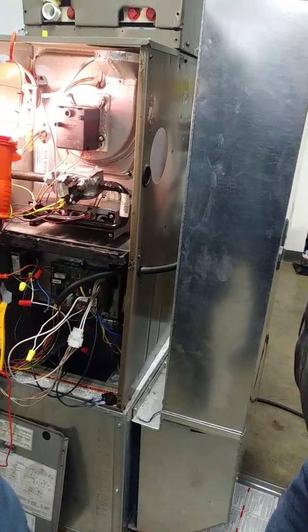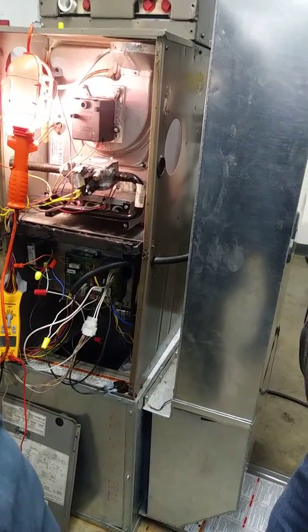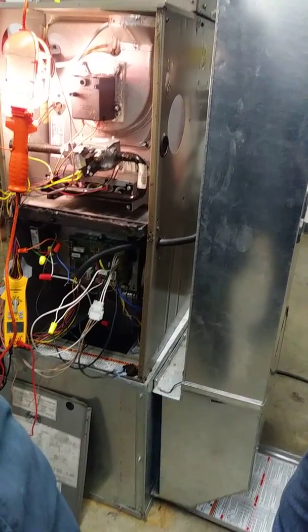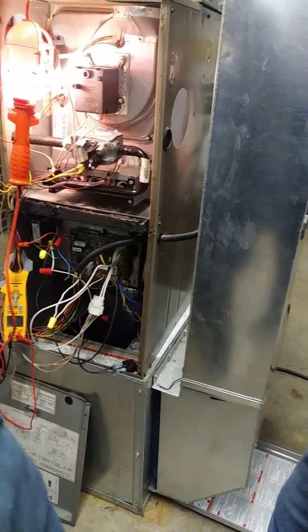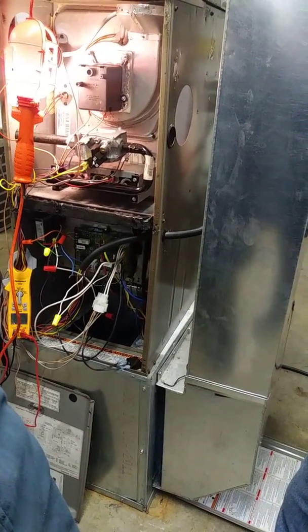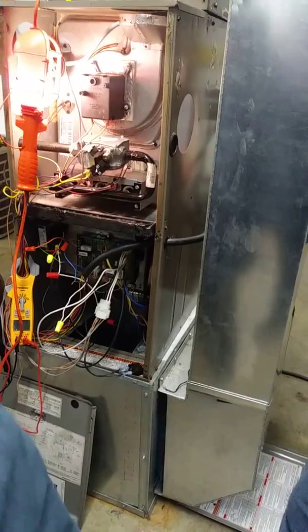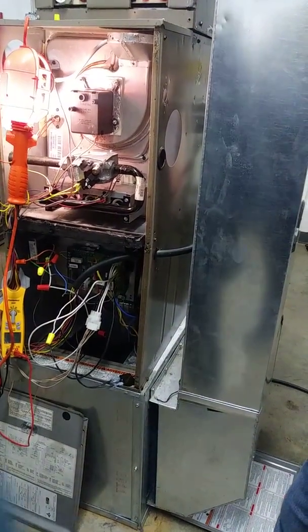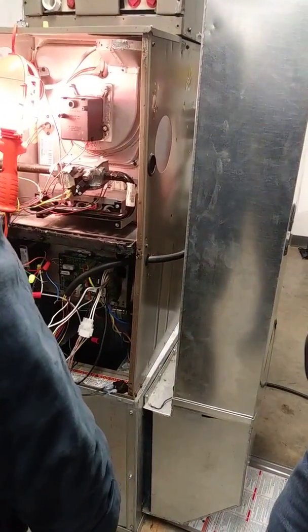But you don't want to overthink it. You heard the gas valve click. Next thing I want to do is check and see if the gas is on. Because it clicks, but it won't keep going further in the sequence. It gets stuck in between that and the flame sensor. Then it shuts off because it's not detecting the gas, it's like a safety switch.